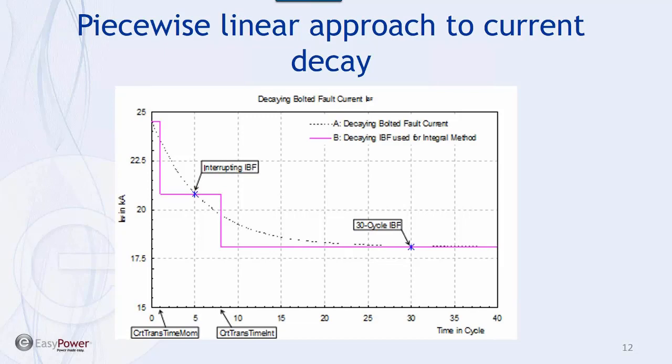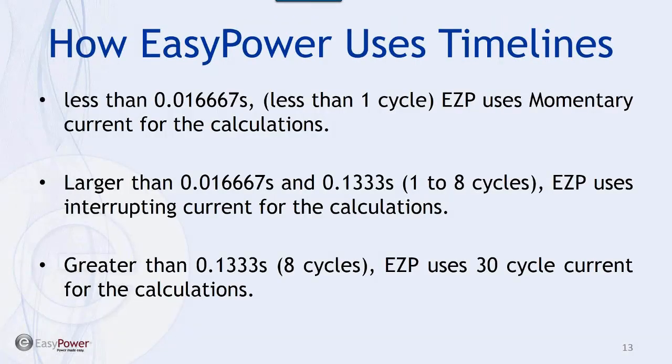It's counting, and it's seeing a lower value for the current, so it's counting at a slower rate, but it's still counting. And if it reaches the point that it has to trip, then we have that value, and it trips, and we take off that branch. So now, let's take a look at those threshold values.